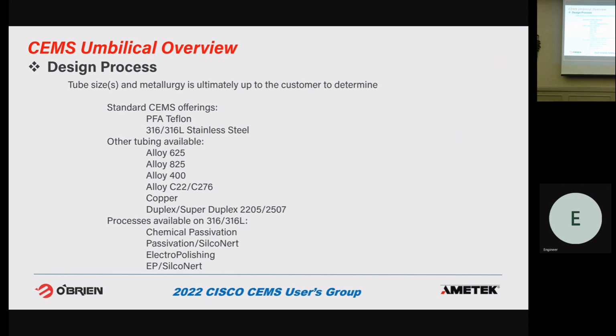EP? Yes, no, maybe. So EPing is kind of the opposite of plating. We're actually taking material off the surface of the tube. What we're taking off we call the free iron. So the iron near the surface, we're taking that off the surface. It's a chemical and electric operation where we're attracting that iron and removing it from the surface. And what that does, it does two things for you. The iron is what is going to corrode, so you're taking that corrosion layer off. And it also tends to smooth the surface out. So in general, we're able to cut the RA, or that surface roughness, in half when we EP. So if it starts off at 40 RA, we can cut it to a 20 RA. And all that helps with getting a better laminar flow. It helps with the adsorption, desorption times.